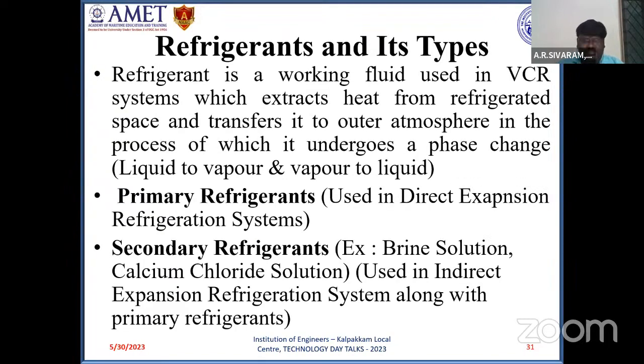Next, I'll give an overview of refrigerants and their types. Normally the working fluid used in any vapor compression refrigeration system is the refrigerant. It extracts heat from one place and transfers it to another place. That is, normally it extracts heat from the indoor space and transfers it to the outdoor space. In this process, it undergoes a phase change. In the condenser, it changes from vapor to liquid, and in the evaporator, conversely, it changes from liquid to vapor as it takes the heat.